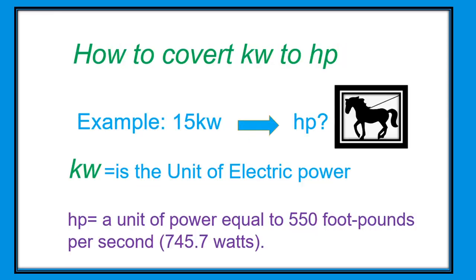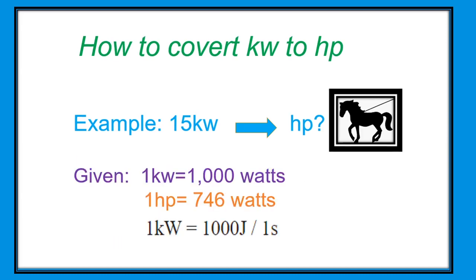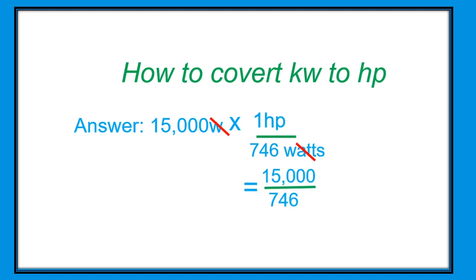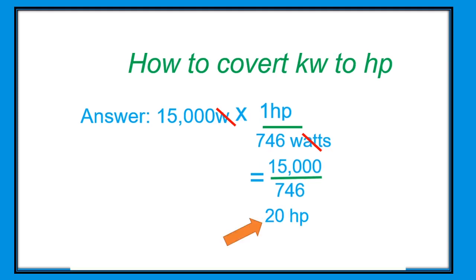Next, how to convert kilowatts to horsepower. Our example is 15 kilowatts. Kilowatt is the unit of electric power, and horsepower is a unit of power equal to 550 foot-pounds per second, or 745.7 watts. Given: one horsepower equals 746 watts and one kilowatt equals 1,000 joules per second. The calculation is 15,000 watts times one horsepower over 746 watts — canceling the watts — so 15,000 divided by 746 equals 20 horsepower.